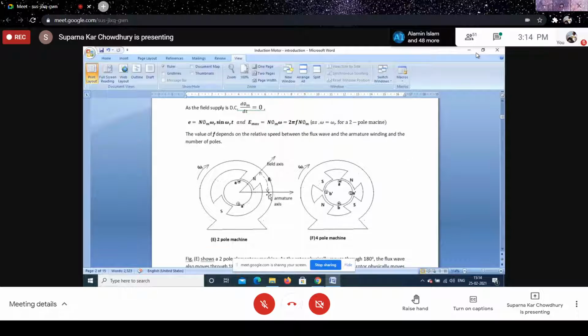What is that relationship? We find that for a two-pole construction, as the armature winding moves through 180 degrees, the electrical wave also moves through 180 degrees. That is, this conductor is near the north pole; once it moves through 180 degrees, it comes to the south pole. So there is a 180 degree movement for the electrical wave as the conductor moves through 180 degrees.